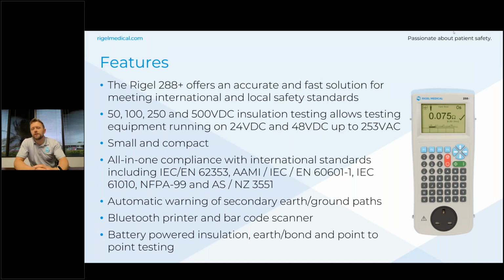We've got full compliance to all the international standards and local codes such as NFPA 99 and IEC 60601, and those standards can even be reconfigured in the test sequences when changes are made. So if the firmware is not the specific version for that code, then limits and the test sequences can be edited by the user and can be more customizable.